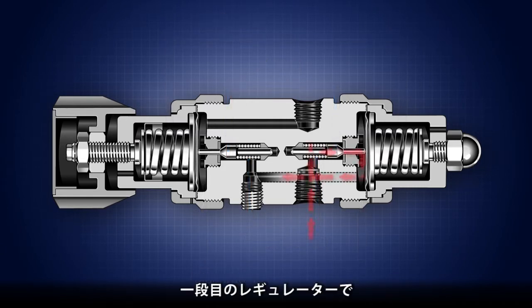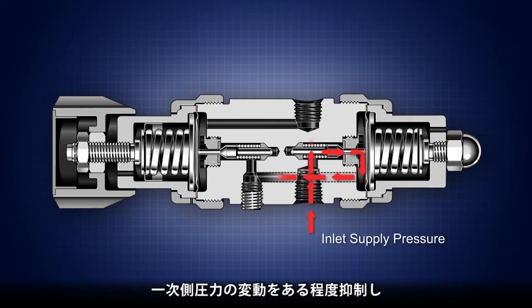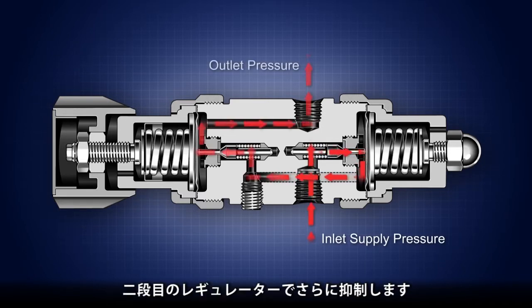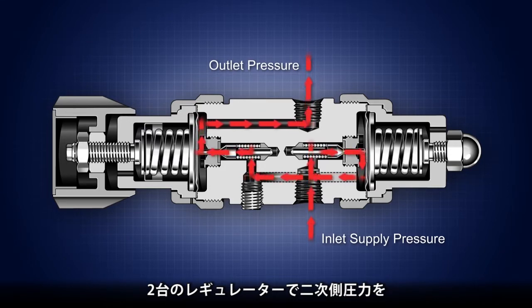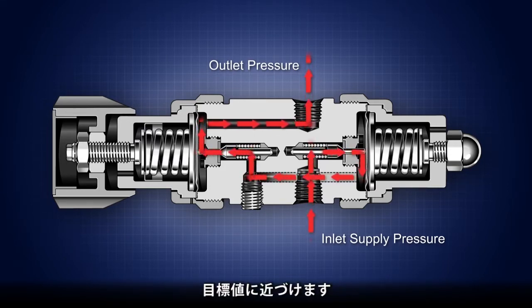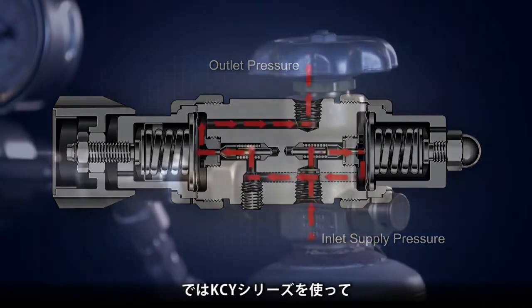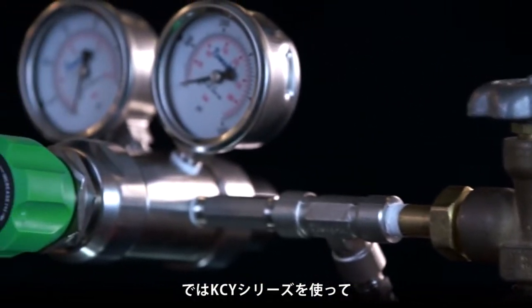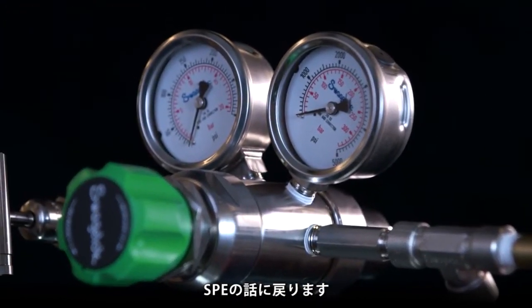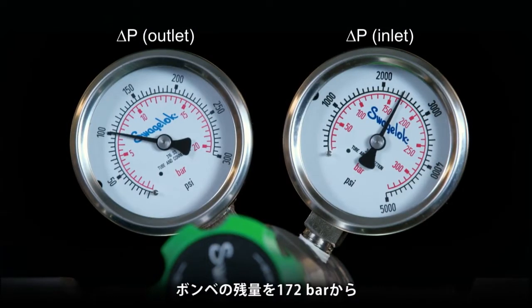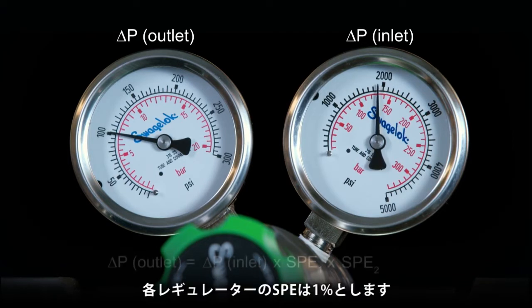The first-stage regulator controls the inlet pressure variation to some degree, while the second-stage regulator controls it further. Together, the two regulators bring the outlet pressure very close to the target. We will use a KCY model regulator and return to our supply pressure effect example. The cylinder empties from 172 bar to 34 bar, or 2500 psig to 500 psig. Assume that each regulator has a 1% SPE.